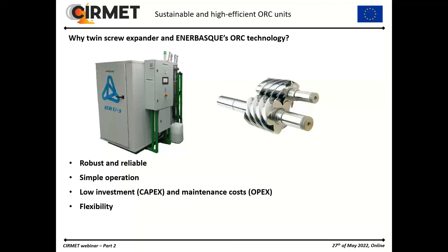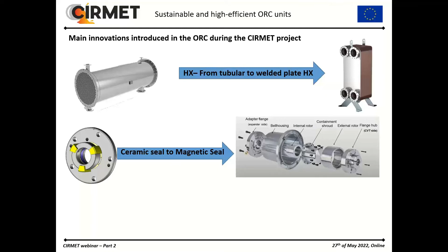The main innovations introduced in the ORC units are the substitution of the current heat exchanger by more efficient plate heat exchangers, magnetic sealing in the expander to avoid refrigerant losses, and substitution of the currently used refrigerant by a less pollutant refrigerant. Tubular heat exchangers are competitive and appropriate for fluids with high dirt content, as they can be easily cleaned. But in the rest of applications, plate heat exchangers are simpler, more efficient, and cheaper. The change of the heat exchanger reduces the CAPEX and footprint of the machine. Indeed, the welded plate heat exchanger of the unit avoids any loss of refrigerant. With the introduction of a magnetic sealing system instead of the traditional ceramic seal, refrigerant leakage disappears and maintenance of the expander unit is reduced significantly, as the sealing system doesn't need any kind of intervention during its lifetime.